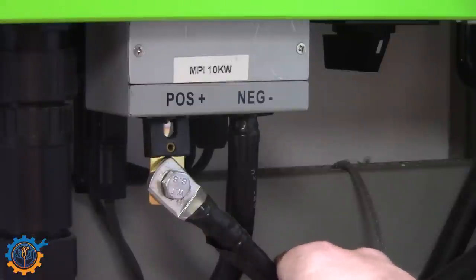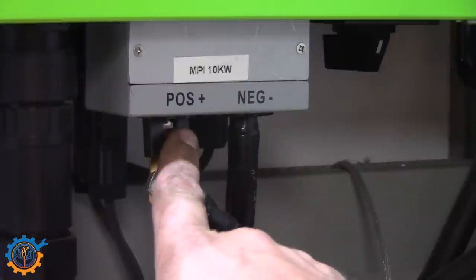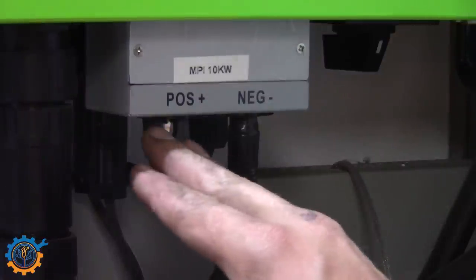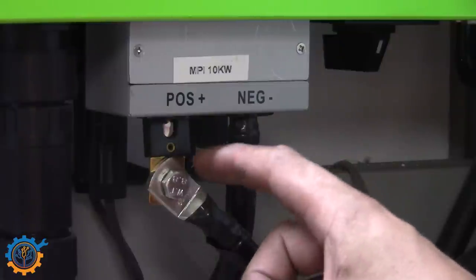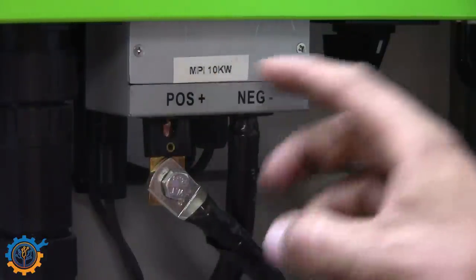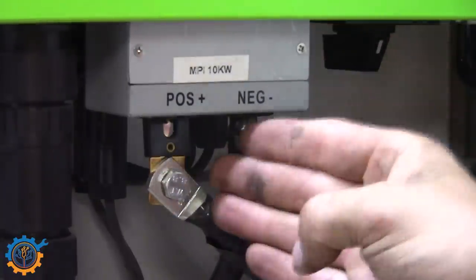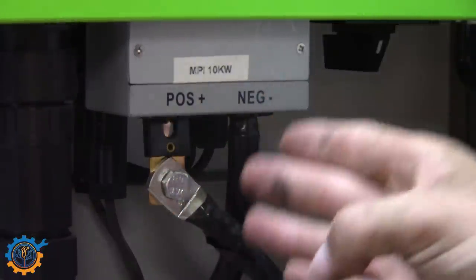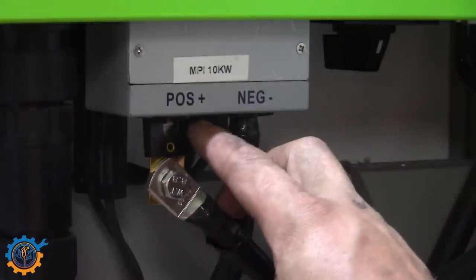This is copper cable so the heat transfers, and I cannot touch this fuse at all. It's bloody damn hot. I have checked the connections, both that one and that one inside there. There is nothing wrong with the connection. They are clean and tied to a really good connection. So the problem is actually the resistance in the fuse.